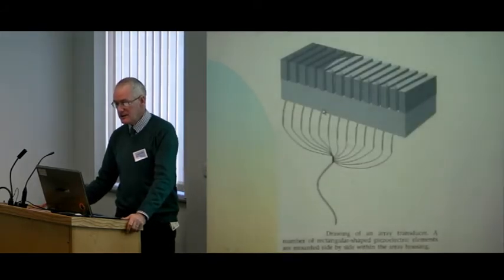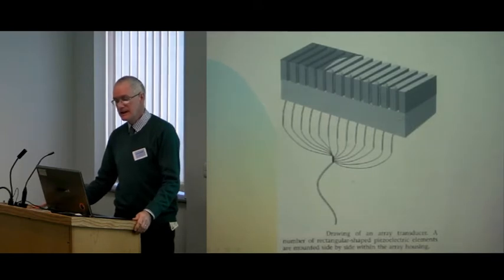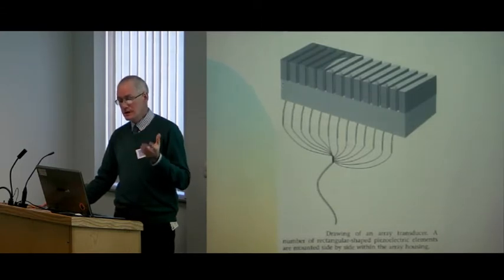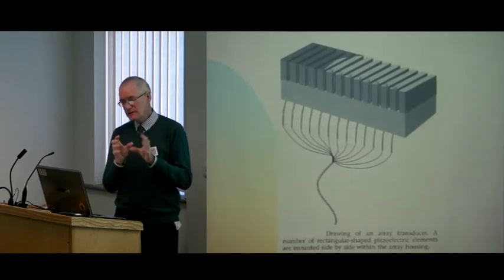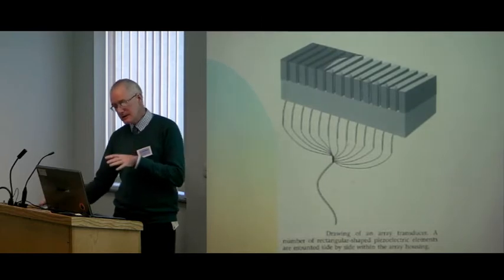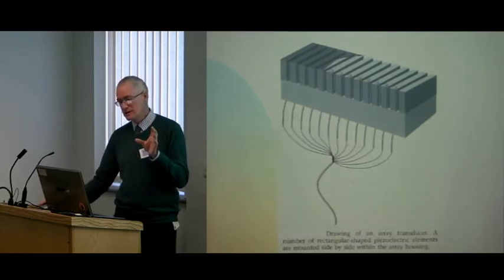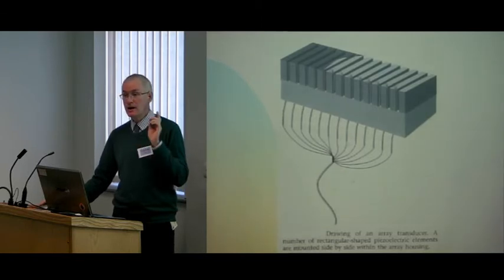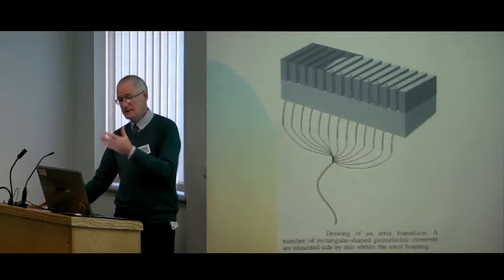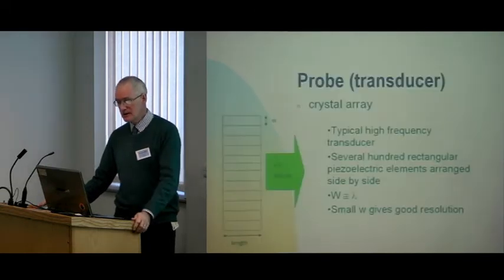This is a very basic diagram of crystals which have a backing substance. That backing substance will allow multi-frequency use of modern probes. Modern probes will have an electrical way of holding onto the crystals so that you can generate different frequencies from the crystals. It's the backing substance which is important in holding the crystal in a certain way that allows those multi-frequencies to be produced by one probe. That's more or less modernisation of probe technology that's happening now.